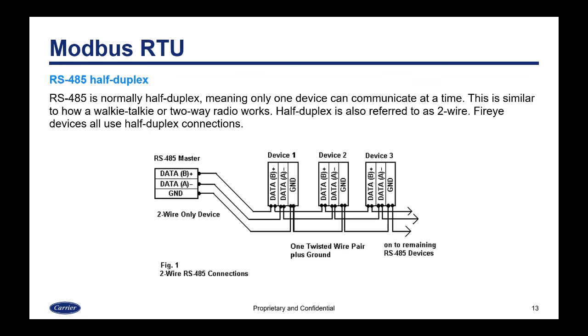RS-485 is normally half duplex, meaning that only one device can communicate at a time. This is similar to how a walkie-talkie or a two-way radio works — only one device can talk at a time until it releases the line. Half duplex is referred to as two wire. Fireye devices all use half duplex connections.